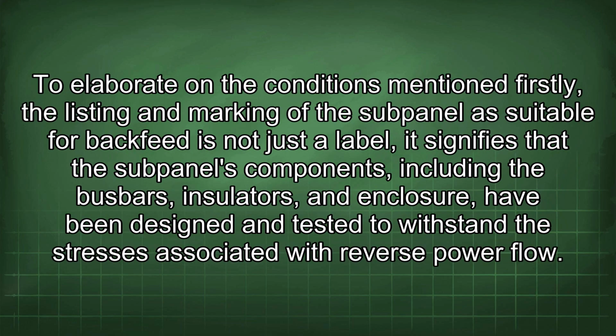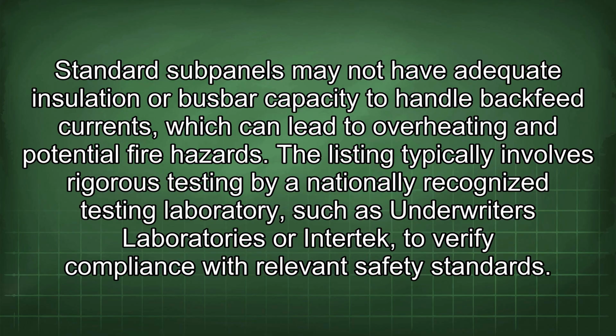To elaborate on the conditions mentioned, firstly, the listing and marking of the subpanel as suitable for backfeed is not just a label, it signifies that the subpanel's components, including the busbars, insulators, and enclosure, have been designed and tested to withstand the stresses associated with reverse power flow. Standard subpanels may not have adequate insulation or busbar capacity to handle backfeed currents, which can lead to overheating and potential fire hazards. The listing typically involves rigorous testing by a nationally recognized testing laboratory such as Underwriters Laboratories or Intertek to verify compliance with relevant safety standards.